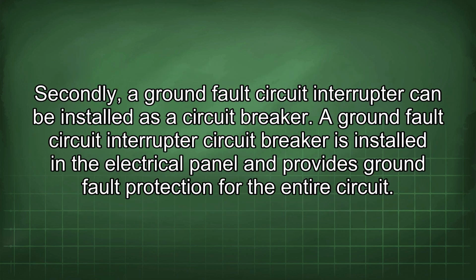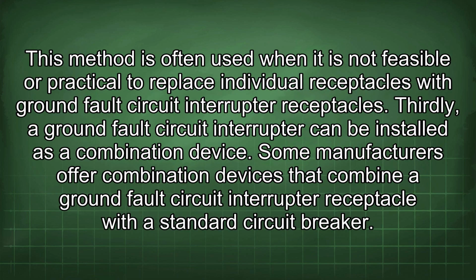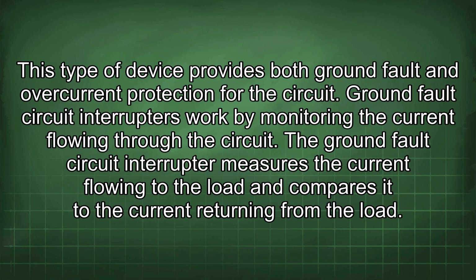Secondly, a ground fault circuit interrupter can be installed as a circuit breaker. A ground fault circuit interrupter circuit breaker is installed in the electrical panel and provides ground fault protection for the entire circuit. This method is often used when it is not feasible or practical to replace individual receptacles with ground fault circuit interrupter receptacles. Thirdly, a ground fault circuit interrupter can be installed as a combination device. Some manufacturers offer combination devices that combine a ground fault circuit interrupter receptacle with a standard circuit breaker. This type of device provides both ground fault and overcurrent protection for the circuit.